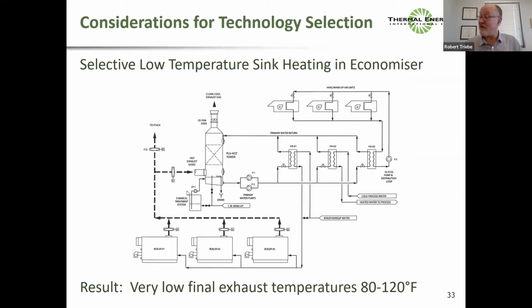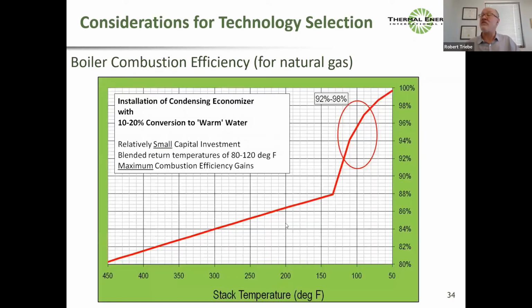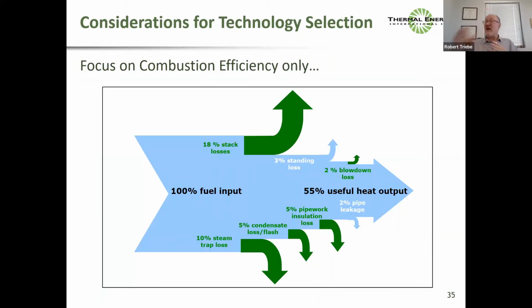So yeah, what's the result? A very low final exhaust temperature of 80 to 120. Got to make the one comment about 100% efficiency. A system installed in Memphis, Tennessee, 100-degree Fahrenheit outside air temperature, boiler exhaust temperature 90 degrees Fahrenheit. So the boiler exhaust was colder than the combustion air. So actually the system was gathering heat from outside air, and that's why it was more than 100% efficient. It was using all the energy we added with fuel and was taking some energy from the hot, humid Memphis air. So the systems can be designed to be quite efficient. And that would be the goal. By separating the sinks, you can achieve much higher efficiencies and get down that curve. Those 20 to 40 degrees are a bigger deal than the whole feed water economizer thing, which people have been playing with for decades. So again, I've been focusing strictly on this.